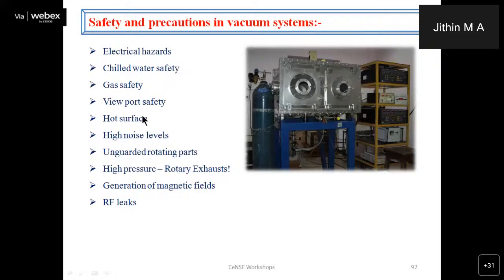And gas safety. Viewport safety. The viewport should have proper thickness, or if there is a chance of the viewport breaking, it can harm a person also. Hot surfaces. Then high noise level, and people who sit in the lab continuously can have hearing problems. And unguarded rotating parts and high pressure rotary exhaust areas have to be carefully addressed. Magnetic fields and RF leaks also have to be carefully addressed, because these things can cause serious health issues in the lab.